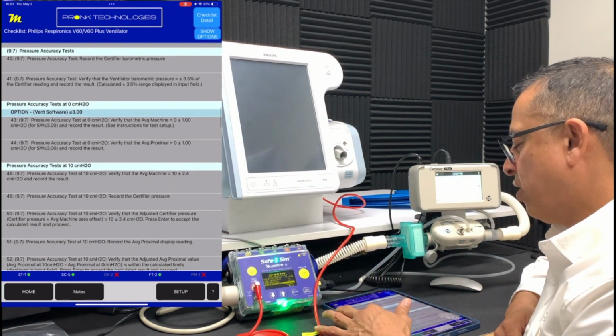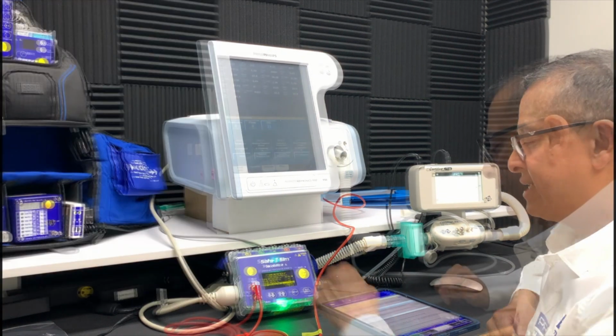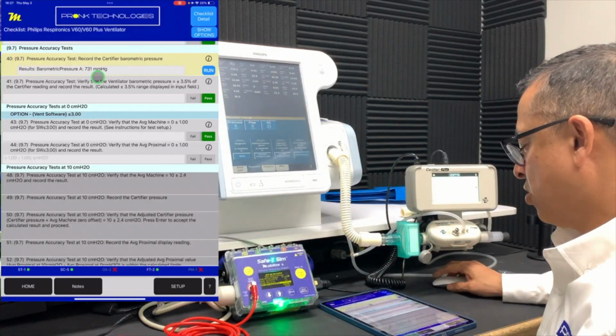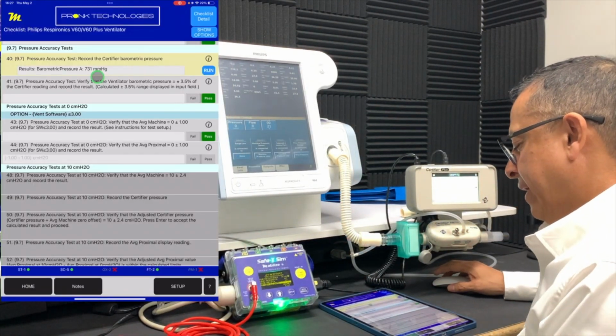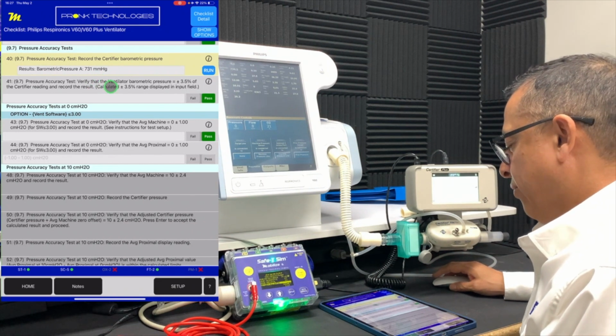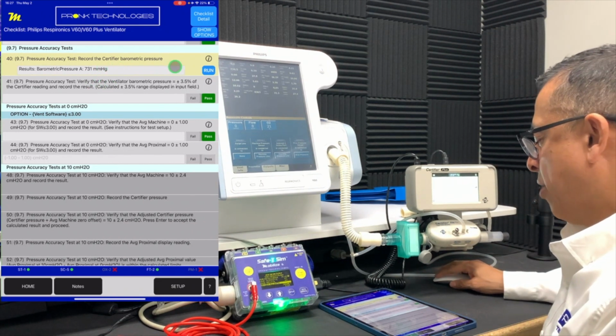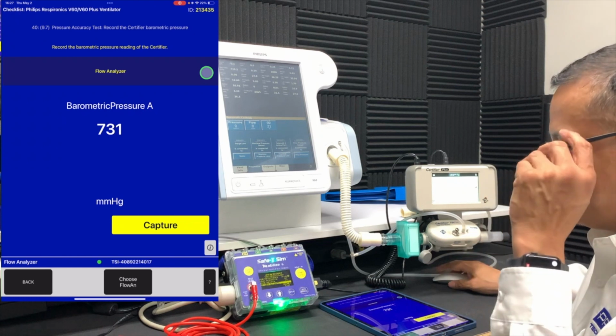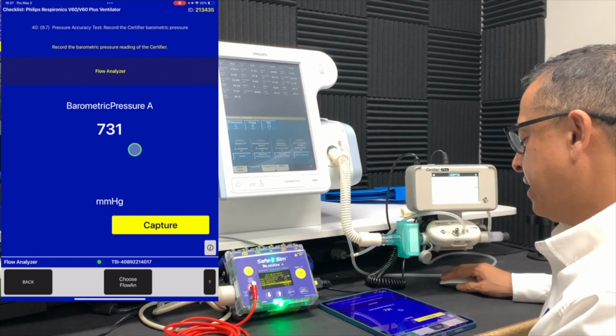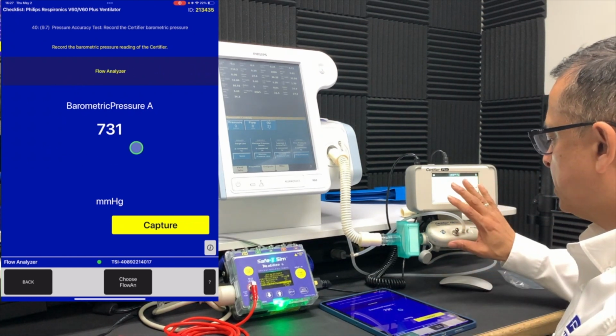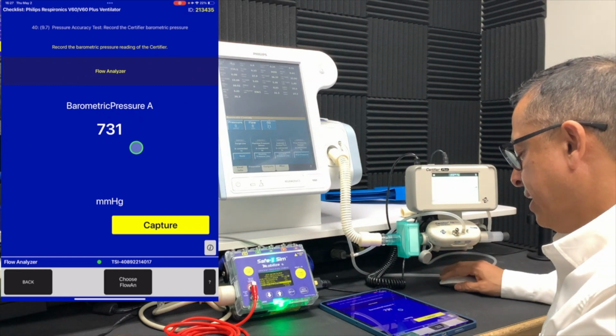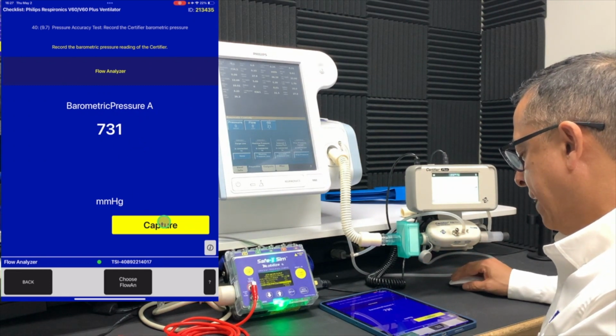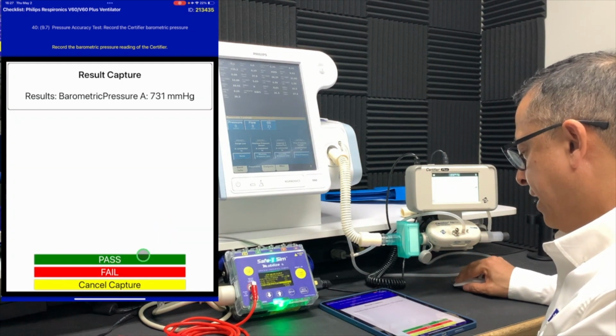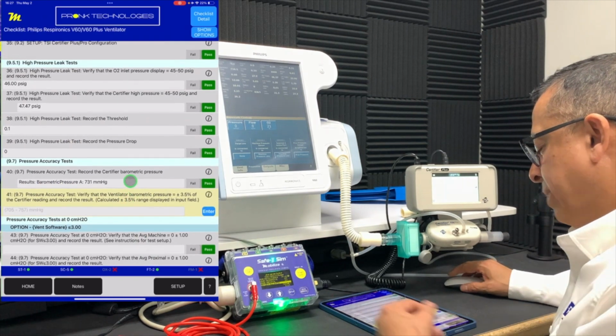So we're going to jump over to do the pressure test next. This starts off by wanting to make sure we record the machine pressure. We actually start with capturing the barometric pressure from the Certifier Plus. So we run that test. You can see the pressure measurement from the Certifier Plus is being wirelessly transmitted to the app, and we see that result here. We can capture that into the report. So that result is within our expected range.